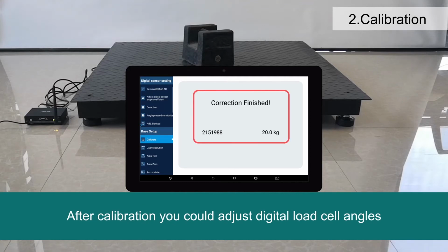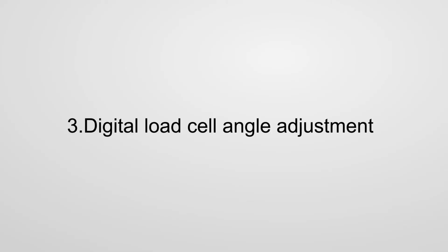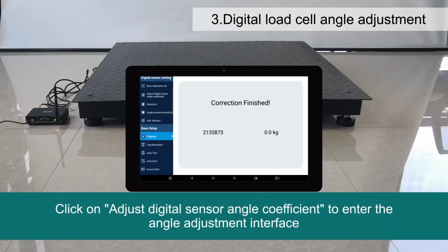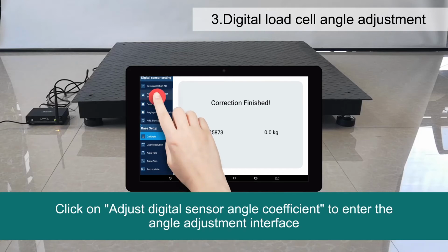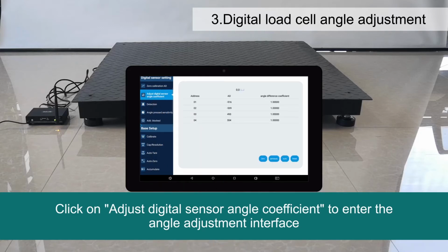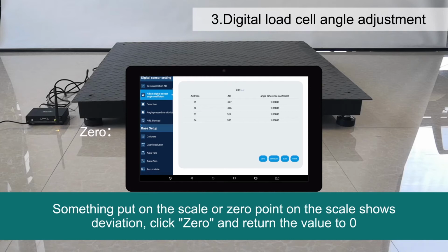After calibration you could adjust digital load cell angles. 3. Digital load cell angle adjustment. Click on Adjust Digital Sensor Angle Coefficient to enter the angle adjustment interface. If something is put on the scale, or the 0 point on the scale shows deviation, click Zero and return the value to 0.